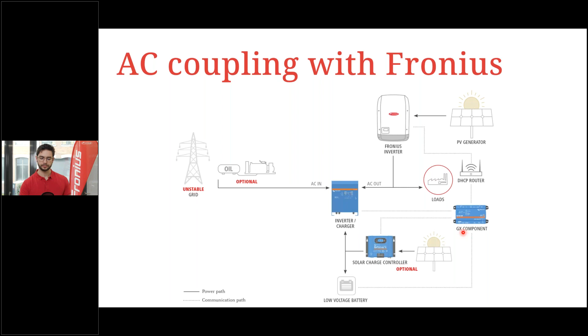Okay, but now comes a really important question, which everyone should raise by now. How do we work the problem out if we have a lot of surplus energy, the battery is full, and there is no grid? What do we do with the energy? And the answer to that question is we have a frequency controlled power reduction, because we need to reduce the output power of the Fronius inverter at any point. Because if the battery is full and we have nowhere to go, the load is not big enough and there is no grid, then we would have an overproduction and kill something, explode something, and that's of course not good.